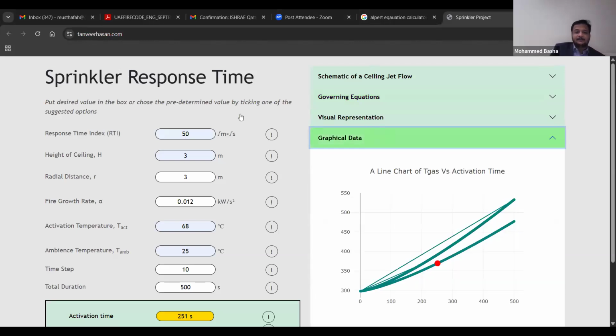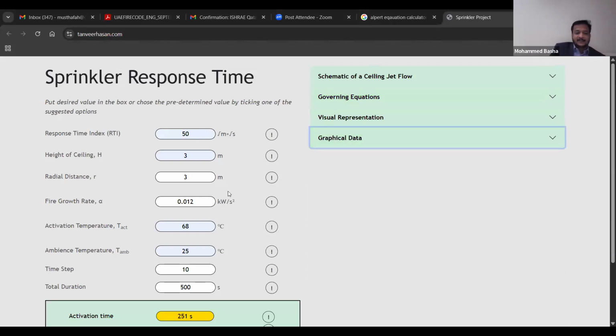Okay, let's see now. Here, it is asking for some inputs. First, you need to put the RTI, the response time index. You can put 50 or you can put 80, depending on the type of sprinkler you are using. Let me put 50, quick response. Height of the ceiling is 3 meters. Let me change it to 6 meters. Radial distance from the sprinkler: let me put 6 meters, 6 meters away.